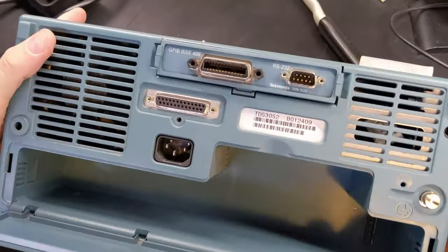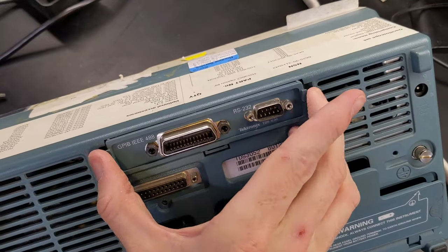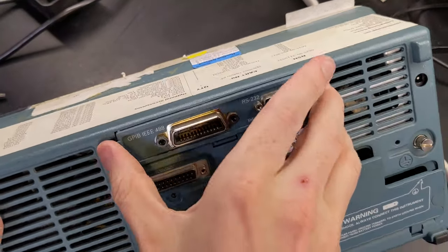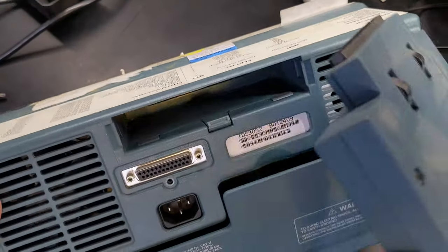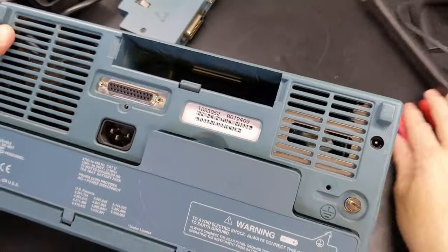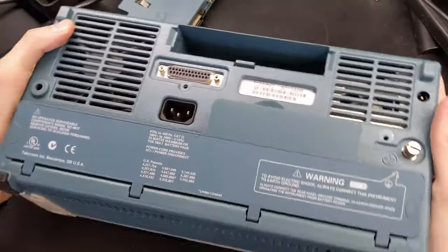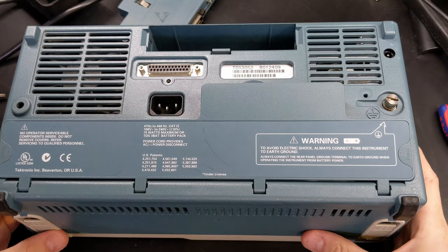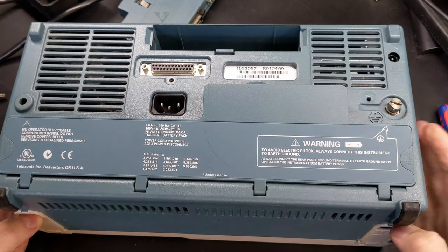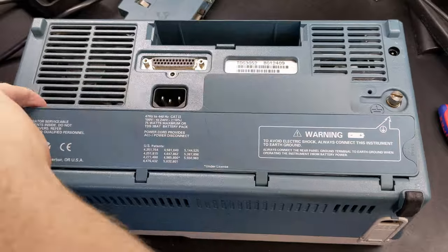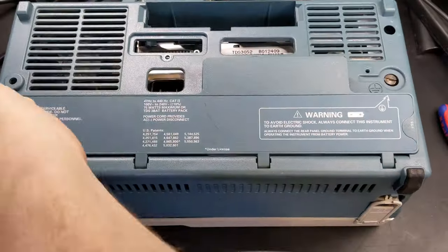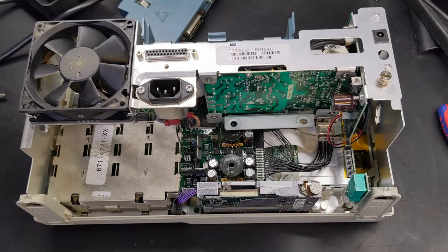If you don't have a battery, they give you a little cool tray for your probe. I'm going to use that to store the pins from the hinge mechanism and the screw from the back. I'm also going to remove this communications module here. Then we're good to remove this entire back panel and we're in.